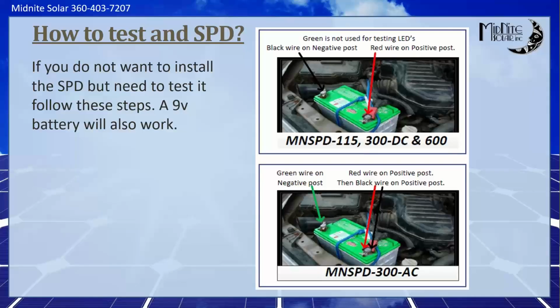Some of the common reasons an SPD doesn't light up: one, it's on the AC input of an off-grid system and the generator is not running, so there's no voltage there. The other one is it's in a PV combiner and the ground doesn't run all the way back to the system. It's got its own separate ground rod. So while it's actually protecting, there is no path for the electricity to go back and turn the LED on. Those are your two common reasons not to get LEDs, but the most common is the one on the AC input. We get calls a lot about one of your pre-wired systems and one of the SPDs isn't lighting up. And it's like, hey, start your generator. Oh, there, lights are on. It's still protecting. Like if there was a lightning strike, it's still protecting that inverter. It's just not turning the LEDs on.